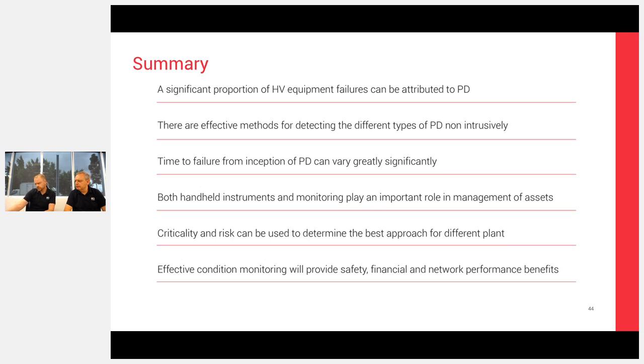Six months annual for medium consequences, when you're referring to online periodic testing. We're not talking offline; when we're talking about the periods, we're effectively talking online. It's quite interesting, in Australia there were lots of companies who would say that they were going to test switchgear every 12 months offline. I don't think it really happens as often as all that anymore. You've also got to understand, if you're testing offline, you're taking switchgear out of service, and you're potentially not testing the cable termination because of the capacitance of the cable. So you wouldn't be able to test cable termination and the VT, and they're two critical areas. But we're talking online in terms of our periods.